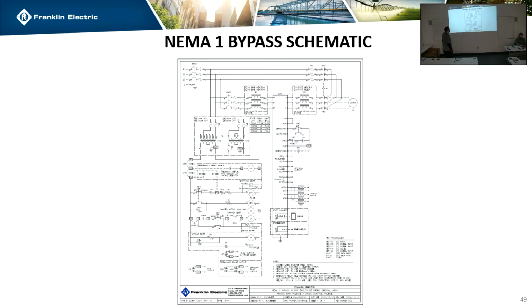See if there's anything on here. This is what I was talking about with the VFD and bypass contactors. So it's got both contactors and they're jumpered together. Your VFD contactor is the one that's going to have a sticker on the back panel right here, and it's going to say motor 1, 2, 3. I think it says T1, T2, T3. That's going to match up with the contacts on the actual contactor. The relay logic I was talking about, we put the VFD contactor and the control relay in front of the forward run command.